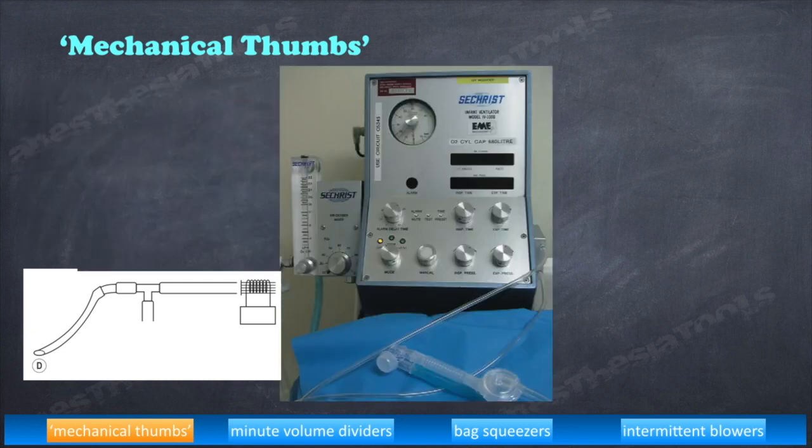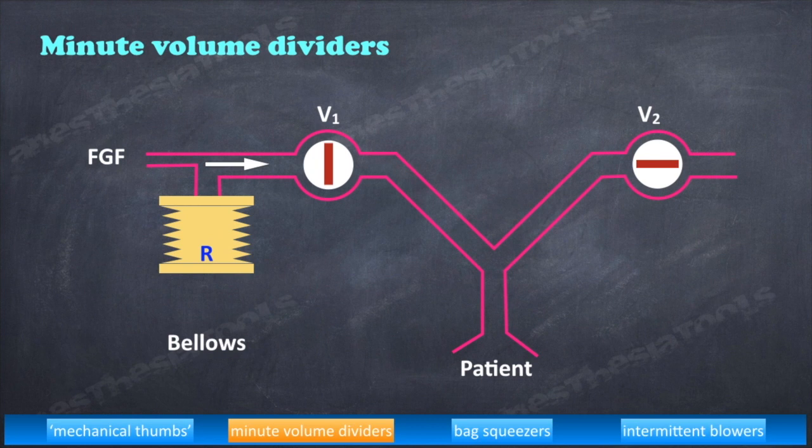In ventilators of this type, the operator's thumb is replaced by a pneumatically operated valve, the cycling of which is determined by the settings of the ventilator controls. Second one is minute volume dividers. A more economical method of using a continuous source of pressurized gas is to feed it into a ventilator system to be collected by a reservoir.